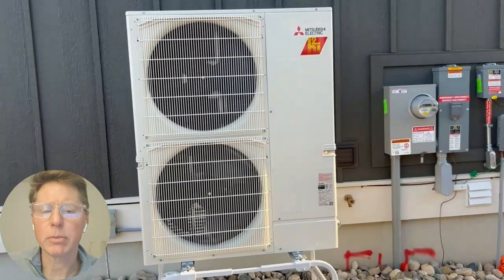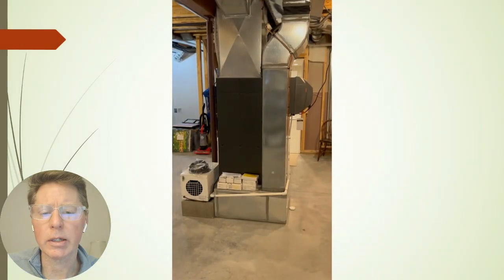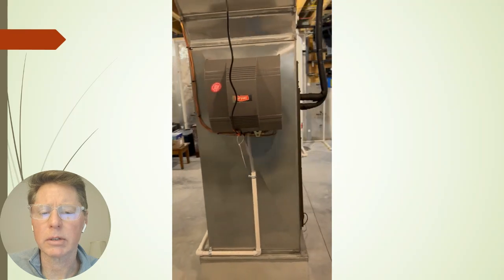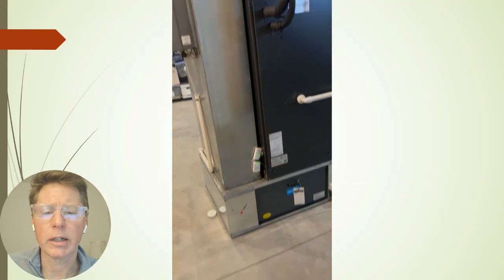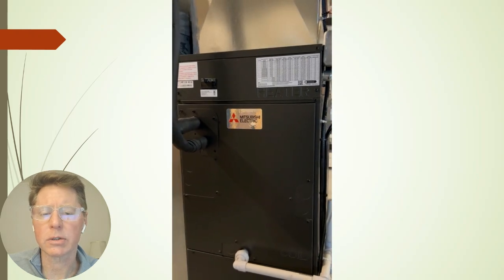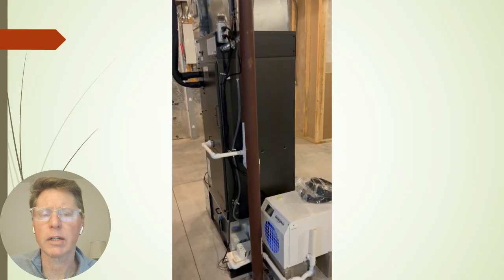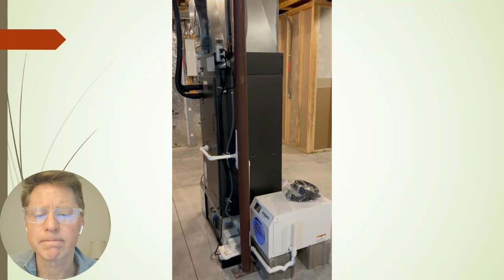For mechanical systems, we have a Mitsubishi heat pump — their cold climate hyper heat unit — with a Mitsubishi air handler ducted conventionally. It has a whole house humidifier and a MERV 11 filter. It also has an electric resistance heater as part of the air handling unit in case we exceed the design conditions, which go down to about minus 13°F — we still have a pretty good COP down to that point. We also included a whole house dehumidifier because even though it's climate zone 6, it's a humid climate.